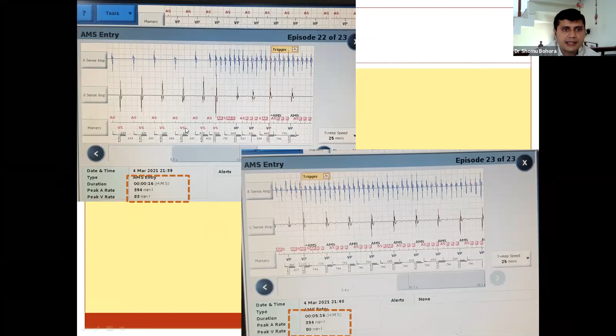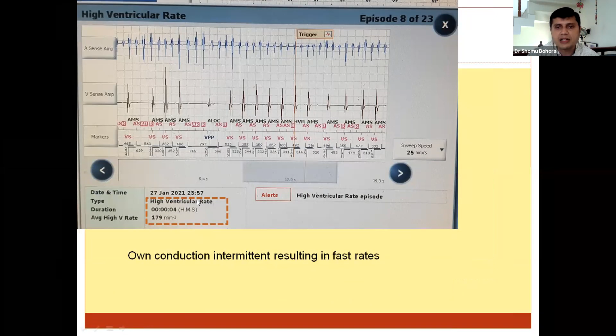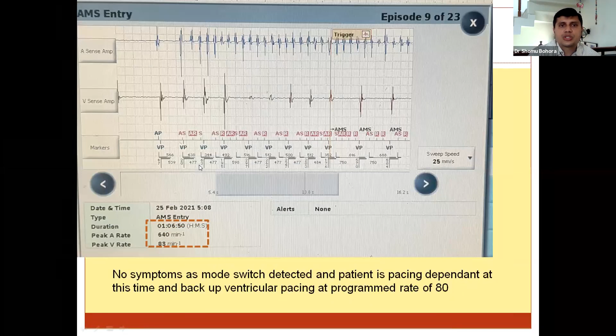Here you can see V pacing going on. And the longest episode was 1 hour, 6 minutes, during which there was a trigger, that is the AMS. Trigger was there, and there was V pace at a lower rate. So this is the upper rate. If the AMS would not have triggered, the ventricular pacing would have continued at faster rates. The AMS triggers, the ventricular pacing decreases to the programmed rate of 80. However, when the patient was conducting on its own, there was high ventricular rate episodes also. So the patients generally become symptomatic when there are high ventricular rate episodes rather than otherwise. So these patients will not become symptomatic, and therefore in this patient no symptoms were there.